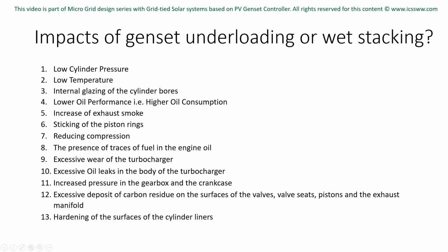Number 2. Low temperature. At low load, engines cool and run at a temperature insufficient to create proper combustion. This also causes fuel to be only partially burned. In addition to deposits, this can lead to a lot of exhaust emissions. Exhaust is the familiar white smoke seen in poorly operating diesel engines. Smoke which is dangerously high in hydrocarbon emissions.